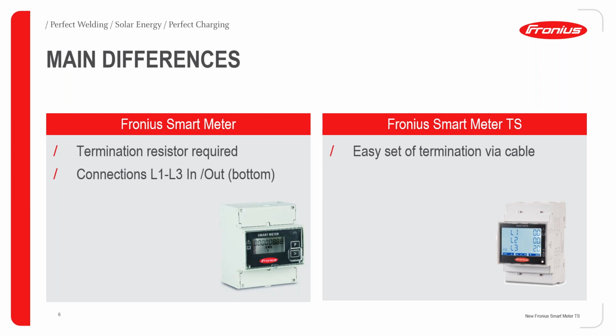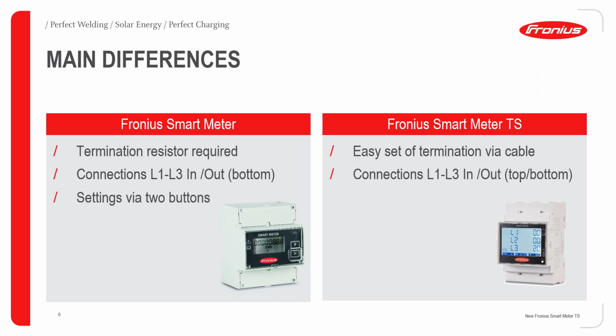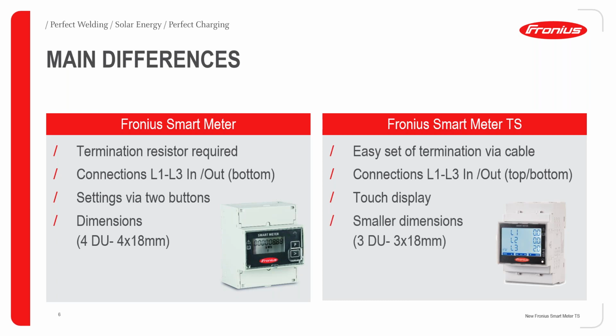And then connections: phase L1, 2, 3 are at the bottom in the old one, and in the new one they are at the top and also at the bottom, on both sides. Settings were made by two buttons. If you see the left-hand side picture, the button P is for program, and the arrow button is for next. Those are the two buttons you used in the past. But here in the new version, it's a touch screen. At the bottom of the screen, you can see three buttons. We will see the details about these three buttons in the upcoming slides. And then the dimension: the old one is 4 times 18 millimeter, and here it's 3 DU, so 3 times 18 millimeter, smaller. The new smart meter is smaller and smart.